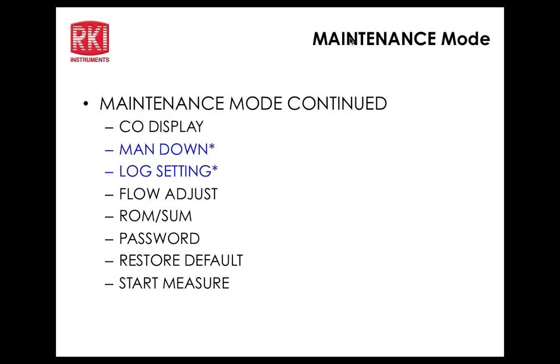The ROM sum number allows you to go into that function. The password is where you would actually set up the password for maintenance mode if you wanted to, and right now it's backdoored to 0006. That's a backdoor, so regardless of what you put in, 0006 always works. If you put in another password, you can still get in with the password you've set up, or with 0006. Then back to start measurement.